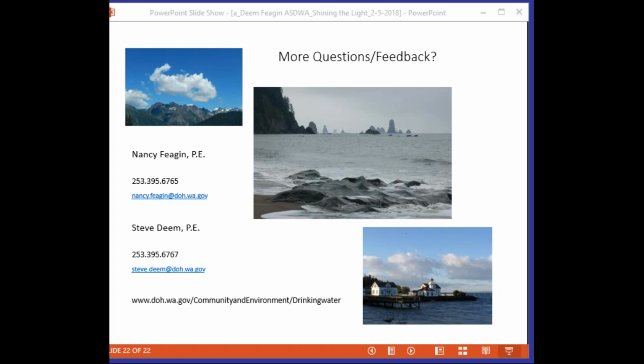And we got another question just a few days ago about the new turbidimeters, the TU5 series. Do you remember that one? Well, we've had a couple, but I'll throw it back at you since you're stringing the question up. So that one was, what about calibration verification of those new online meters? There's some rods that you can use as secondary standard, but they cost like $900 or something like that. But you get 3 rods.